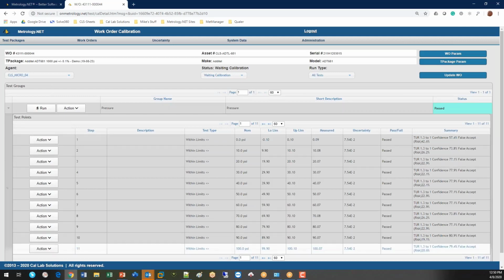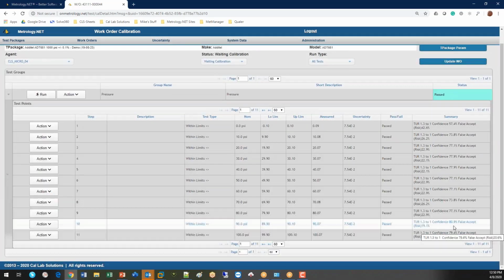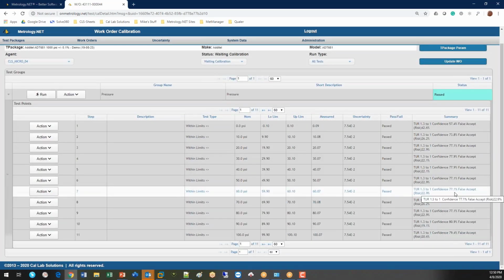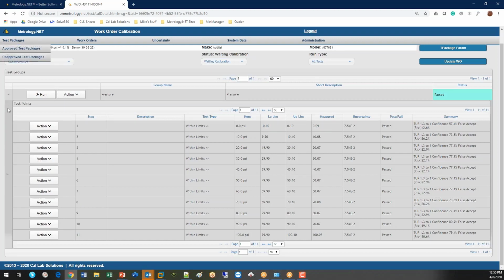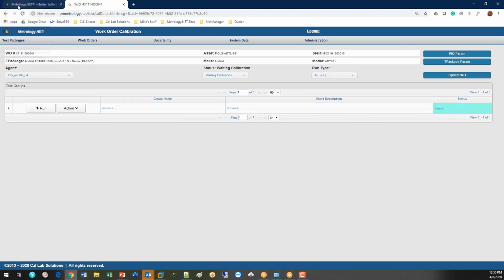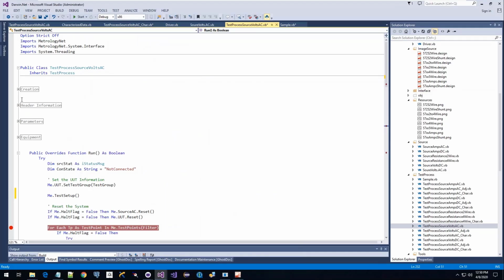That looks really bad, but look at your confidences. If you're trying to hit a 70%, all but this one data point hits that confidence point. So it's doing your confidence analysis while it's running the calibration, at the process level, not at the instrumentation level.